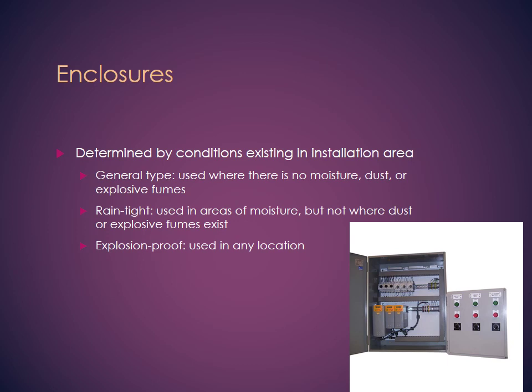enclosures. Again, the code requires us to have enclosures for all the wiring. We don't want to have any exposed wiring, especially for heavy duty equipment. And some of them require that no moisture comes inside. If moisture comes inside, it will probably ruin your connections. So you don't want to have dust or explosive fumes. If we work in a power plant and we have a gas leak, we might want leak-proof containers that cannot have any water or gas going inside, because if you notice, there's a lot of control included inside the enclosures. Also, there's rain tights.